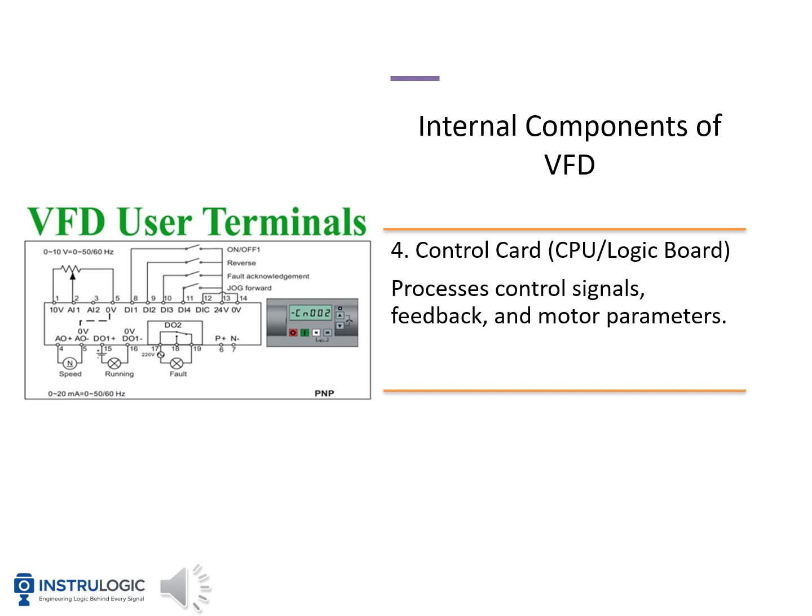Now let's look at the fourth important component of a VFD, which is the control card, also called the CPU or logic board. The control card is the brain of the VFD — it processes all control signals, feedback, and motor parameters. It receives inputs from sensors and user terminals and decides how the inverter should switch to achieve the desired motor speed and torque. The VFD user terminals allow connection of analog inputs for speed reference (0–10V or 4–20 mA), digital inputs for commands like start, stop, forward, and reverse, and outputs for status indication like running or fault. The control card uses this information to control the motor accurately and safely.